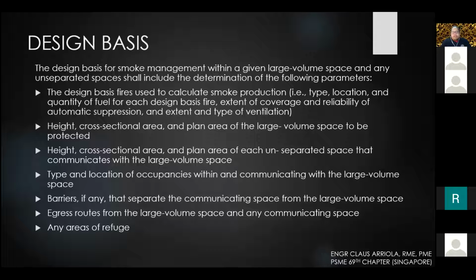The design basis fires used to calculate smoke production: type, location, quantity of fuel for each design basis, extent of coverage and reliability of automatic suppression, and extent of ventilation. Why do we need this? These are important parameters for us to calculate the exact volume of air that we want to extract, because the exact volume of smoke produced is based on the source of fire or fuel.